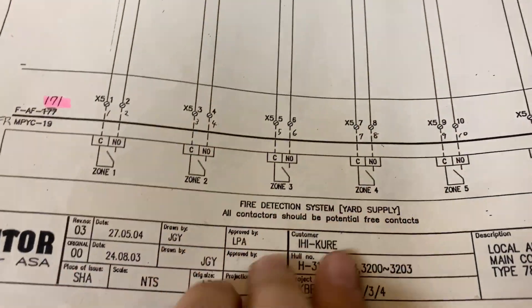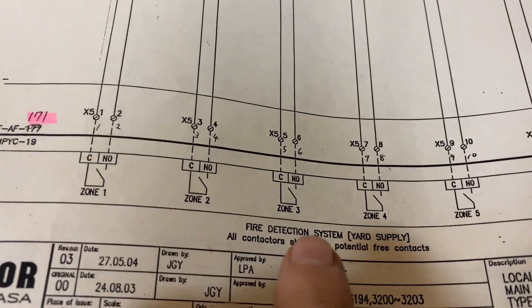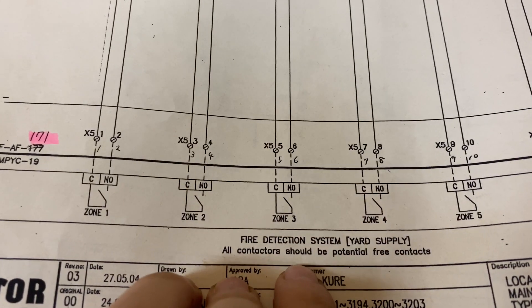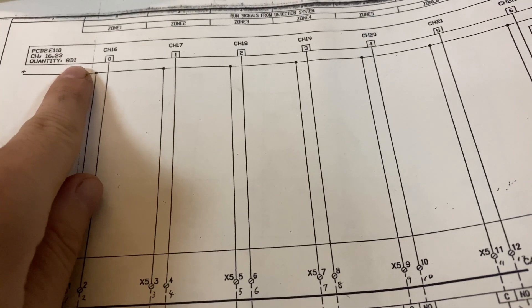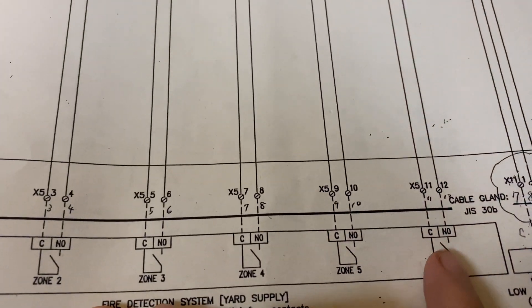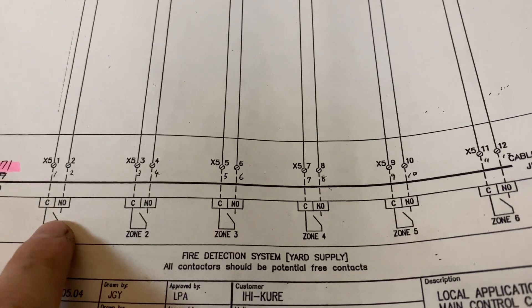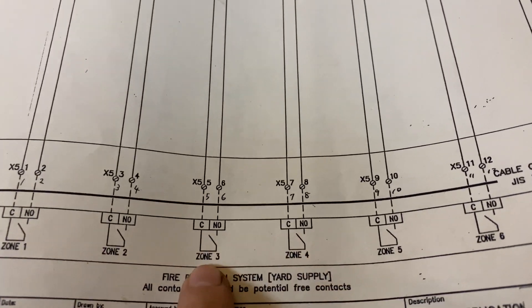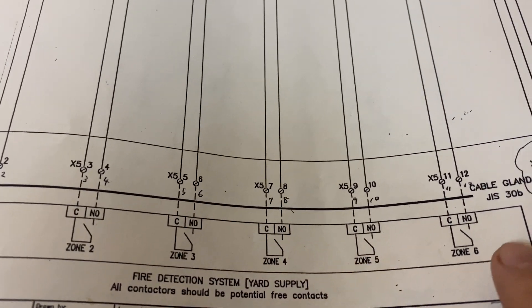This is our wiring diagram for the water mist system. I'm focusing on the pages with a link on the fire detection system — this side is the fire detection system and this is the water mist side. Based on my understanding, the zones are divided into six areas: main engine, auxiliary boiler, generator room port side, starboard side, incinerator, and purifier area.